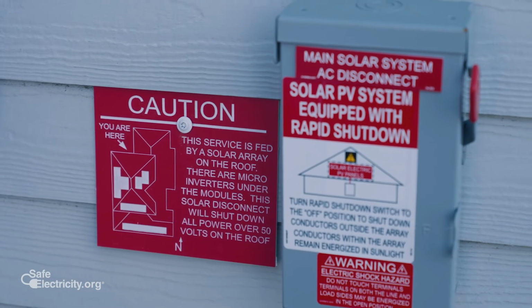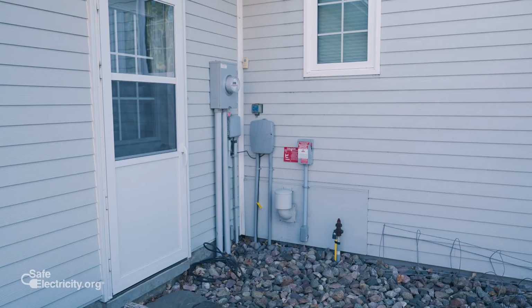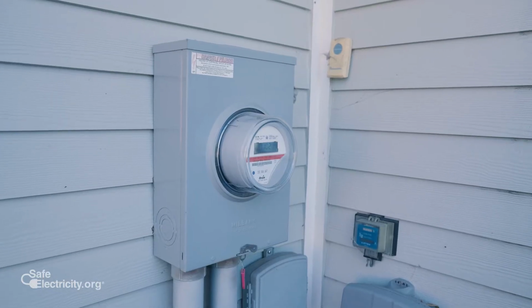Installed properly, there should be a sign that says there is an alternate energy source there. Examples would be a generator, solar panels, battery backups, things like that, if it was done properly. The odds of it being done properly on small standby generators that you can buy at local box stores are very limited. I've said this before, the meter is not a switch, it is not a disconnect point.